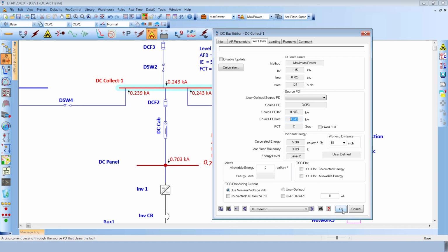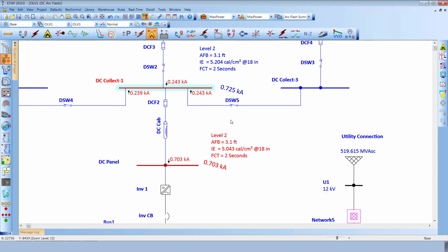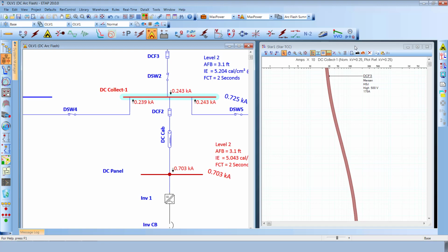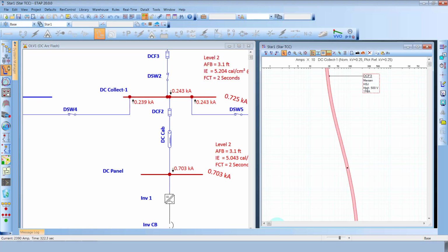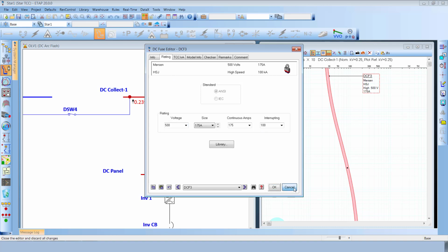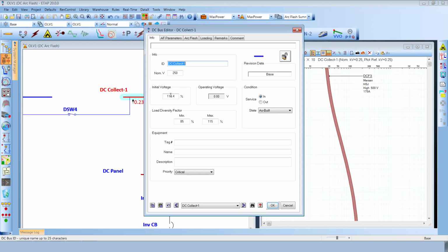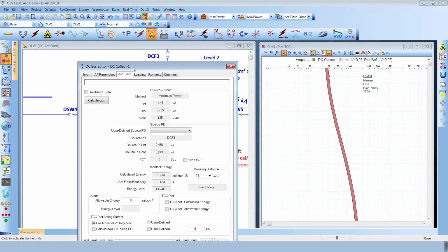This can be visually shown in a time current curve in ETAP using the star menu. For that purpose, I have created a star view that shows the manufacturer curve of DCF3 that is connected to the combiner box for this fault location. As you can see, the current is actually 243 amps, which could obviously result in a longer clearing time.